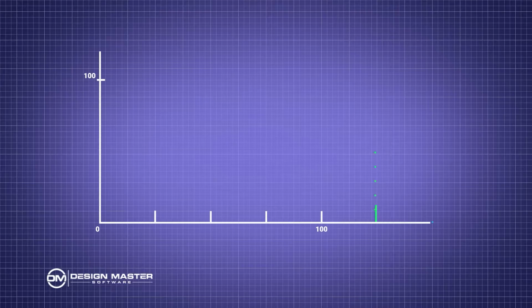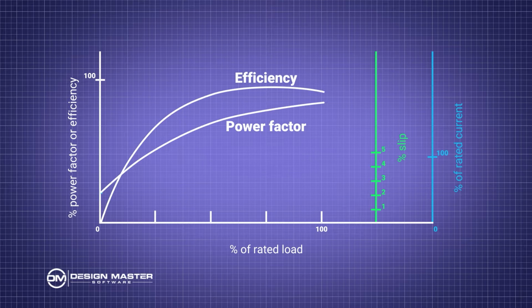And there's a curve here which shows you that as the motor is coming up to load, the power factor changes. And so the relationship between the current and the power is not precisely following in a linear fashion to be useful. Now, if the manufacturer measures all these characteristics and gives you a table, well, then you can use the amps. But otherwise, you can't just use them without all that information tested.